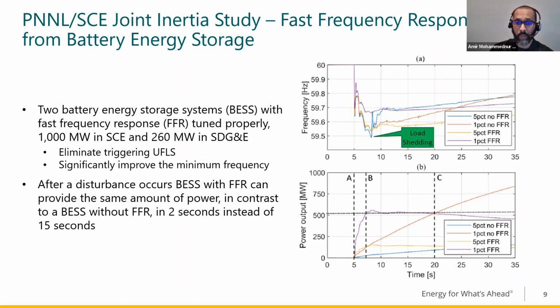The plot below shows the response of the 1,000 megawatt energy storage resource modeled in the study, and how a 1% droop setting without FFR can output a large amount of power, but with a significant delay of 15 seconds, compared to when FFR was enabled, which was able to output the same amount of power in about 2 seconds, fast enough to contribute to the initial part of the frequency drop and arrest the frequency nadir. Next slide.